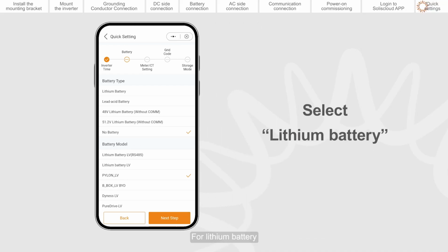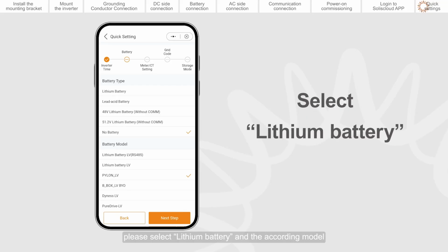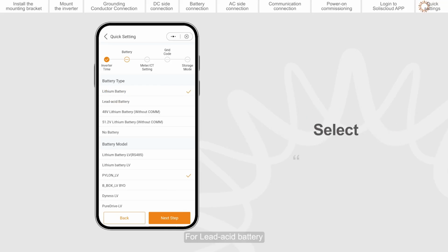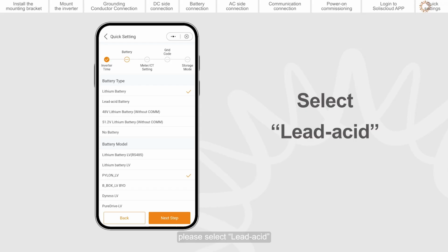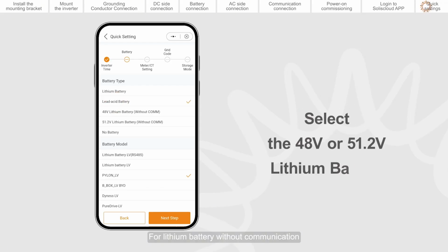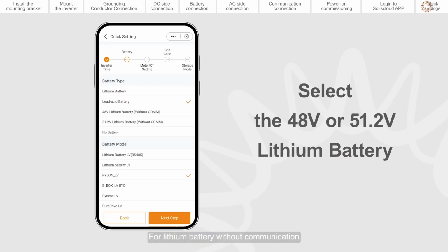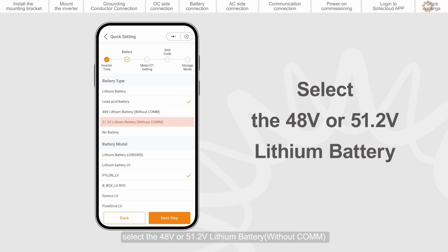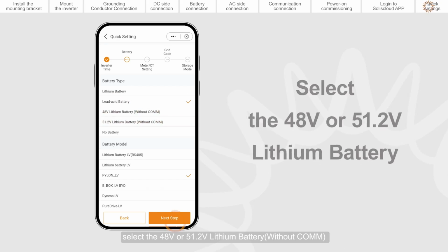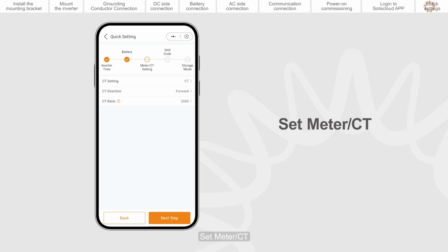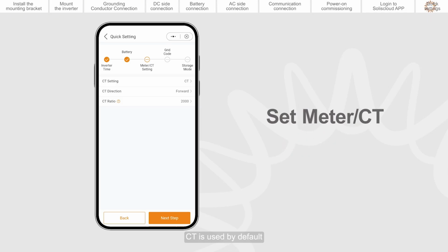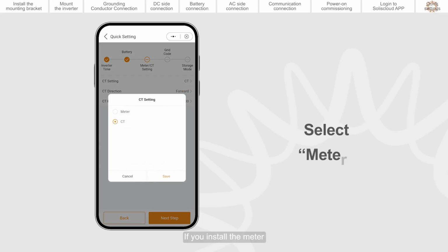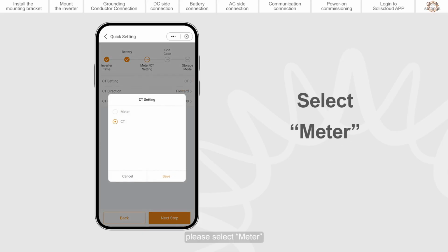For lithium battery, please select lithium battery and the according model. For lead acid battery, please select lead acid. For lithium battery without communication, select the 48 volts or 51.2 volts lithium battery. Set meter as CT. CT is used by default and CT ratio is set to 2000 by default. If you install the meter, please select meter.